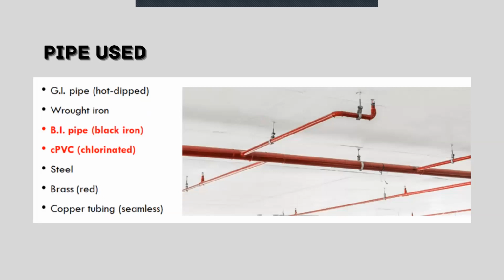Sabi ng ating fire code, we can use GI pipe, galvanized iron pipe, provided that it is hot dipped. We could also use wrought iron, BI pipe (black iron pipe), and PVC, particularly the CPVC or chlorinated type, which is light orange in color. We can also use steel, brass, and copper tubing, provided that the connection is seamless, hindi flared connection.